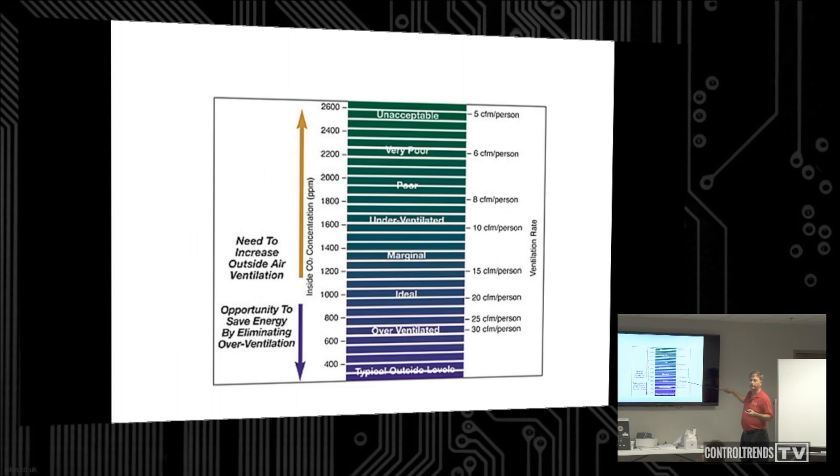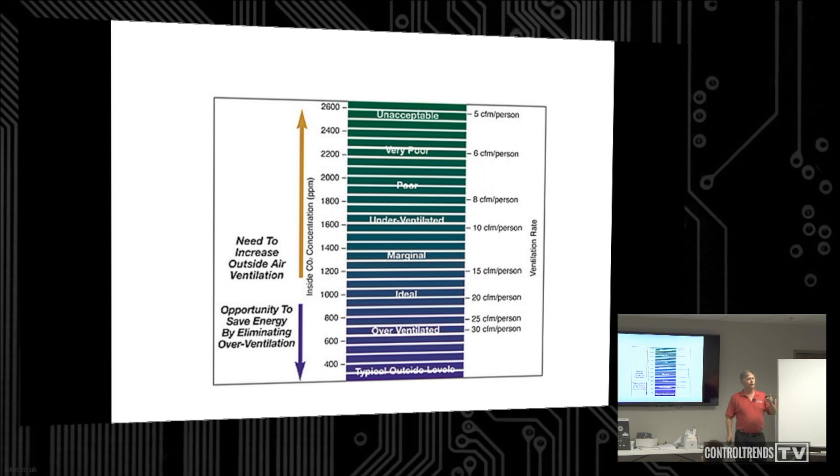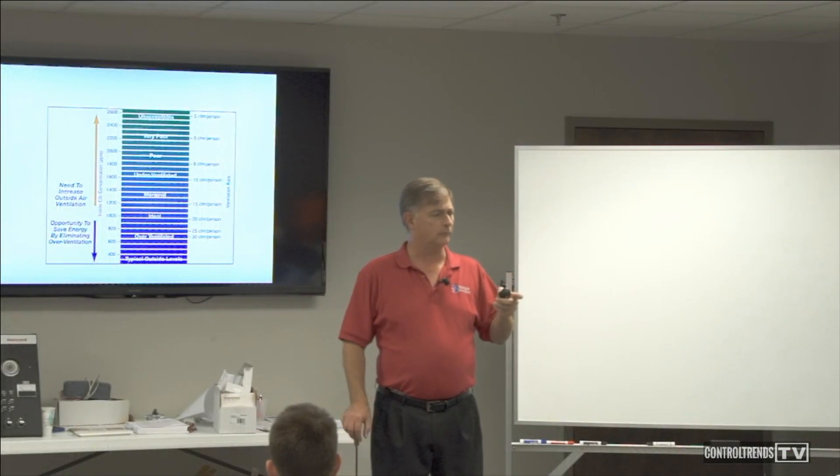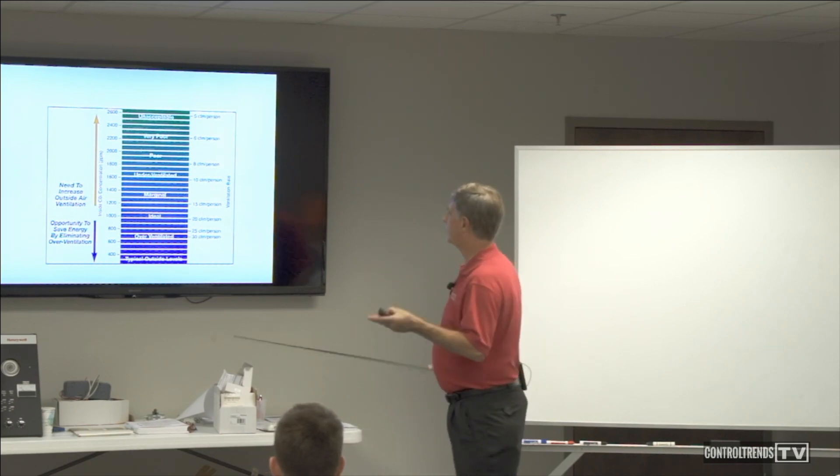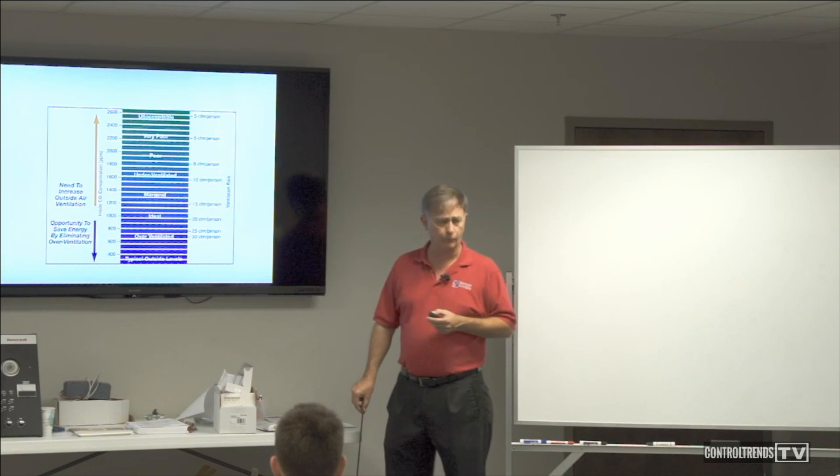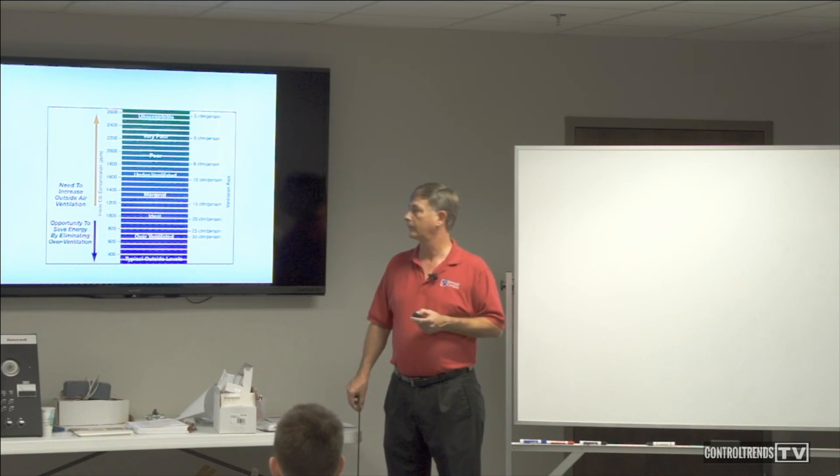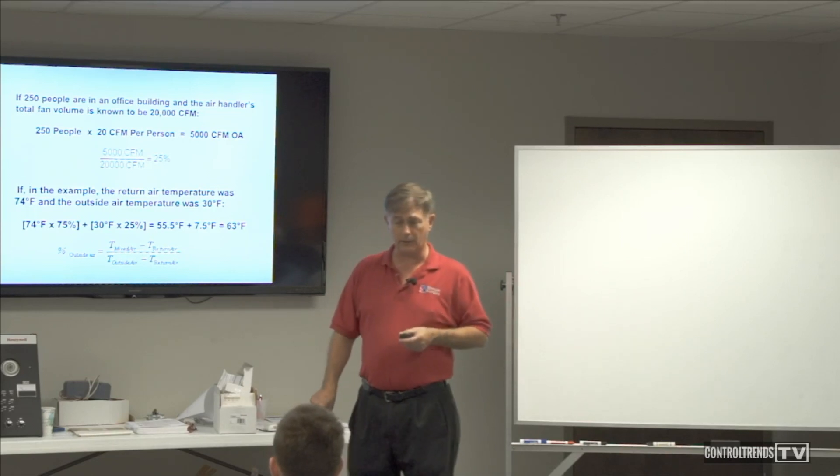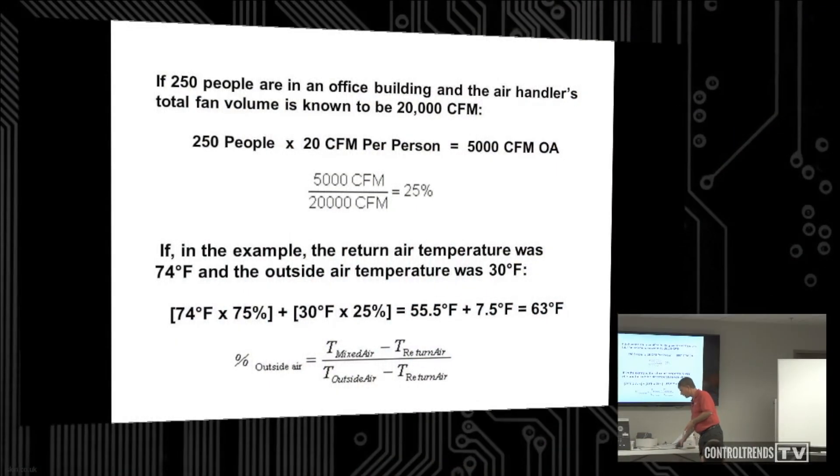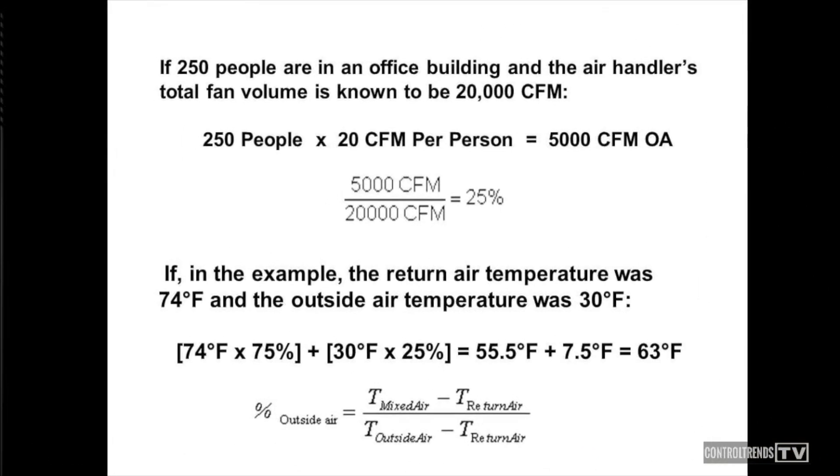That corresponds to this table right here. And we have guidelines in our codes, mechanical codes, that for office, for restaurants, for schools, they recommend a certain CFM per person of ventilation air, of fresh air, that outside air. Depends on the application. Now, we can do a little bit of math to see where we are because sometimes just because we have outside air dampers on our buildings, doesn't mean that we have the proper amount of outside air.